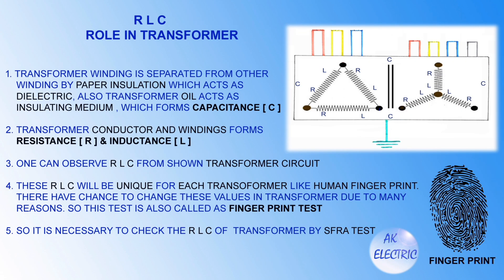Transformer winding is separated from other windings by paper insulation which acts as a dielectric. Transformer oil also acts as an insulating medium, forming capacitance C. The transformer conductor and winding form resistance R and inductance L. These RLC values are unique for each transformer, like a human fingerprint, and they can change due to many reasons. So this test is also called the fingerprint test, and it is necessary to check transformer RLC by SFRA test.